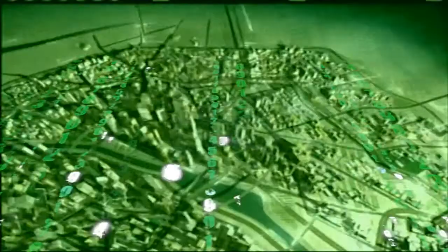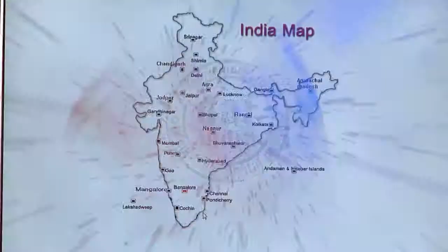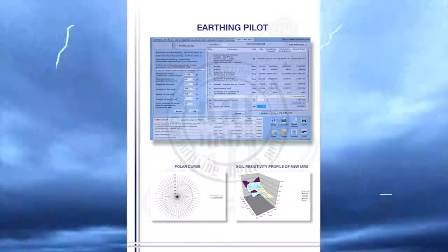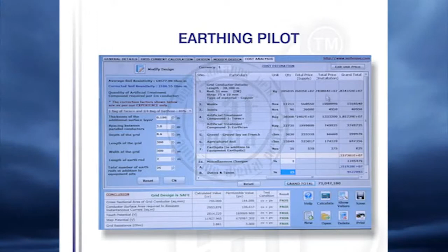Team SGI has undertaken a mammoth task and deciphered Publication 94 of National Soil Survey of India, compiling countrywide, hectare-wise top soil resistivity data to provide key information to earthing design engineers from a central command center. Earthing Pilot homogenizes information of IEEE, API, British standards, NFPA and Indian standards into an economic drag-and-drop user-friendly software. Semi-skilled manpower can create safe earthing with respect to cross-section, surface area, dangerous potentials and resistance, with a background database aiding designers and prompting suitable options.